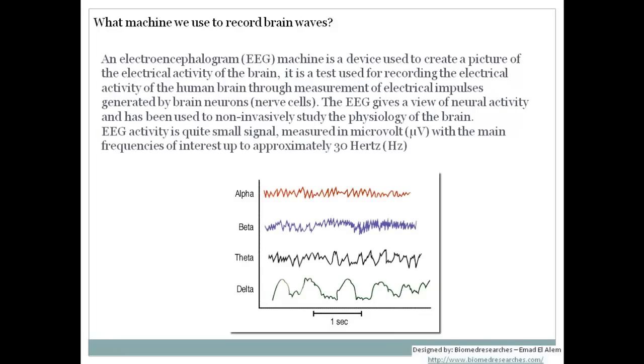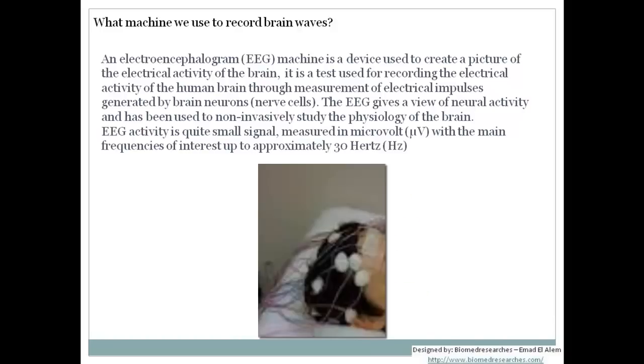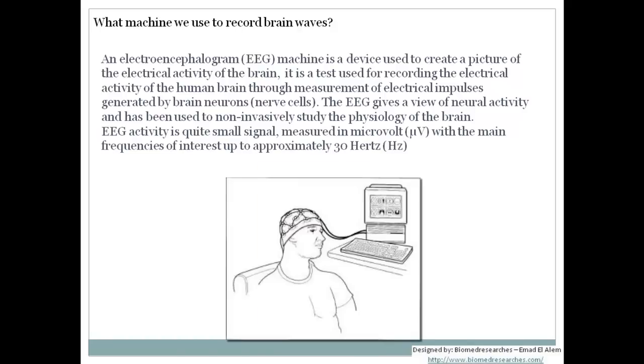The EEG test is a non-invasive test, meaning we don't hook the electrodes directly to the brain. We connect the electrodes to the patient's scalp, and from there the electrodes transmit the signal to the amplifier. The EEG signal is a very small signal — typically in microvolts — so it must be amplified to make it readable, then sent to a display device where doctors can view and report it.